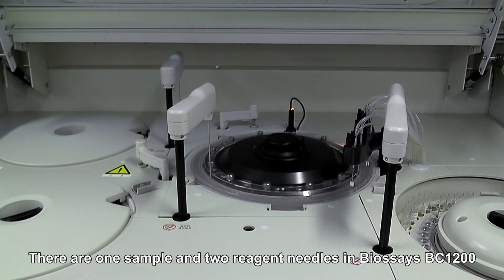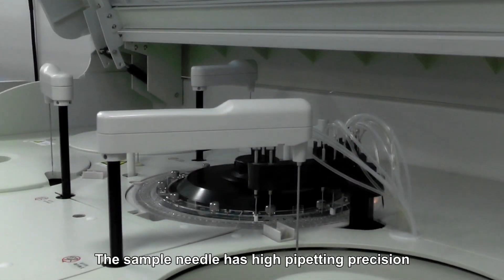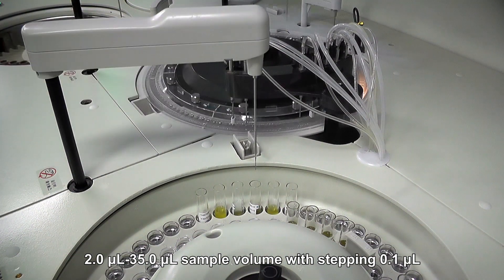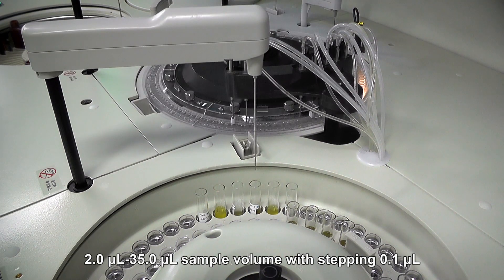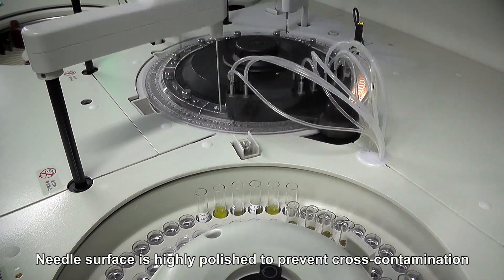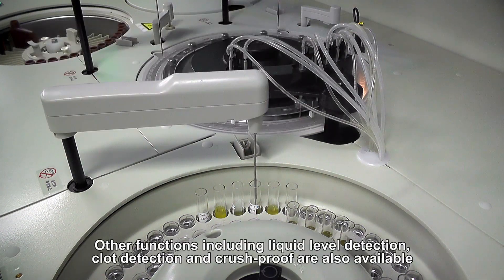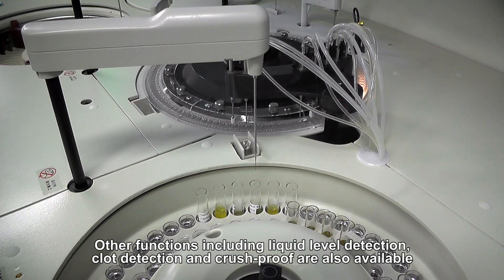There are one sample and two reagent needles in Biossays BC1200. The sample needle has high pipetting precision, with 2.0 microliters to 35.0 microliters sample volume with stepping of 0.1 microliters. Needle surface is highly polished to prevent cross-contamination. Other functions including liquid level detection, clot detection, and crush-proof are also available.